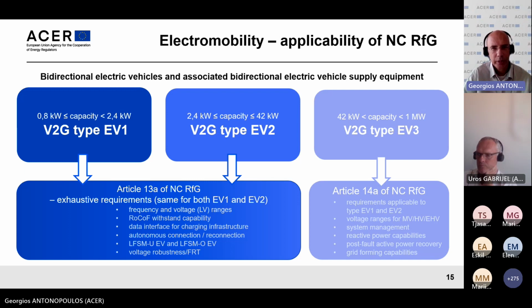And then of course voltage robustness and fault ride through capabilities. For EV3, we have a new article 14A, which again has requirements effectively the same as for type EV1 and EV2. In addition, we have some voltage ranges for medium voltage, high voltage, and extra high voltage, plus system management provisions, reactive power capabilities, post-fault active power recovery, and grid forming capabilities.